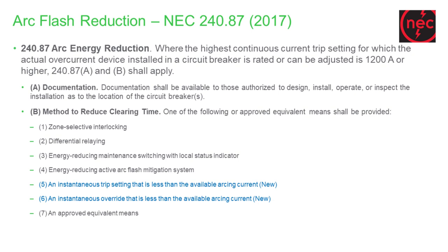Let's see what the standard tells us. NEC 240.87 recommends that if we are dealing with 1200 amp breakers and higher current, we must use one method of reducing the arc or reducing the clearing time. The recommended methods are: zone-selective interlocking, differential relaying, energy reduction maintenance switch (ERMS), using arc flash protection, and recently added — instantaneous override overcurrent, and a fully equivalent method, which is a written agreement between the engineer and operator.